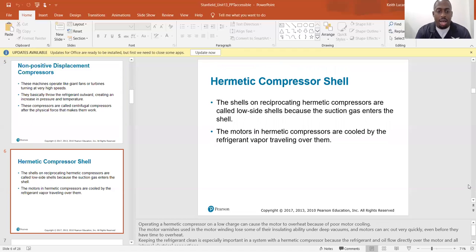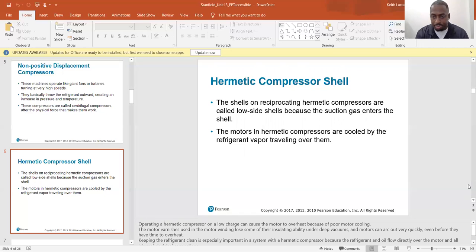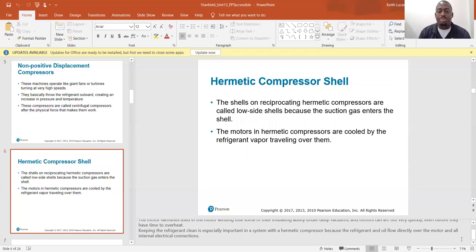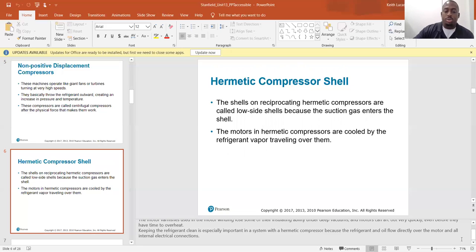Hermetic compressor shells: operating a hermetic compressor on a low charge can cause the motor to overheat due to poor motor cooling. The motor varnishes used in the motor winding lose some of their insulating ability under deep vacuums, and motors can arc out very quickly, even before they have time to overheat. Keeping the refrigerant clean is especially important in a hermetic compressor system because the refrigerant and oil flow directly over the motor and all internal electrical components.